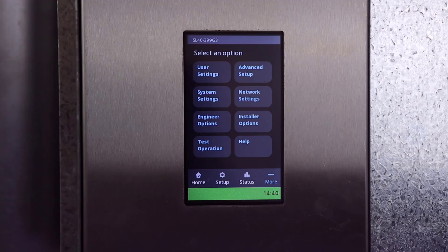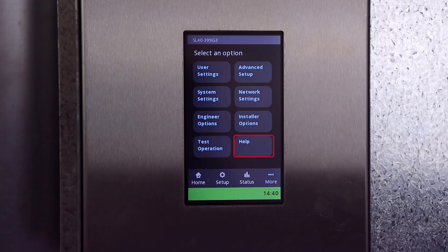Test Operation is where you can test, monitor, and control the fan speed, as well as monitor the flame current during a call for heat. Test Operation can be used to control the firing rate and is the recommended place for commissioning and performing a combustion analysis. Help is a new page that provides a link to our technical information portal, where you can find service parts, videos, documentation, and concept drawings. You can enter the link into a browser or simply scan the QR code. If you require further clarification on specific settings, please review our V10 controller manual found on our technical information portal.